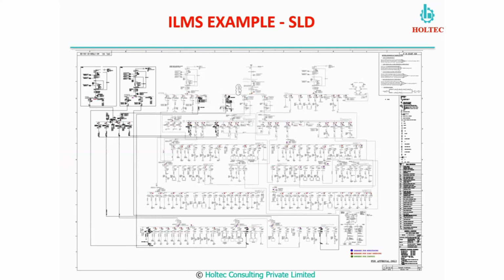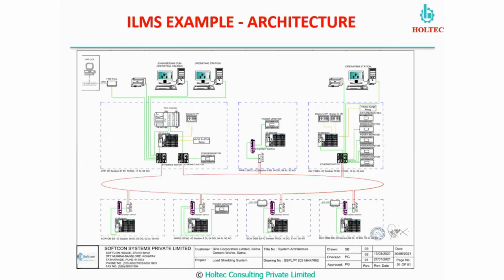So the controls means generator controls, tie breaker and bus coupler controls, and bus capacitor controls. Then we have load shedding breakers, which we can operate based on the priority, and for taking any decision, we do the measurements on the various sources, various branches, various tie feeders. We can do the power monitoring also, and the loads also, the power monitoring. This is the control architecture for our designed ILMS system. We have a dedicated controller for this task. It is independent of all other activities. This is not your process controller, plant process controller.